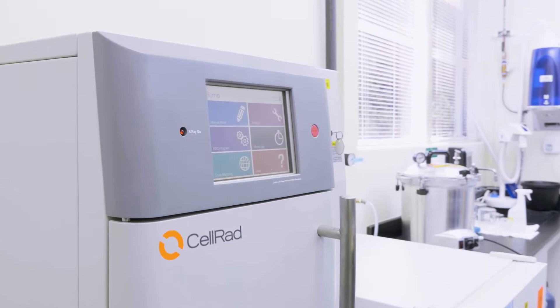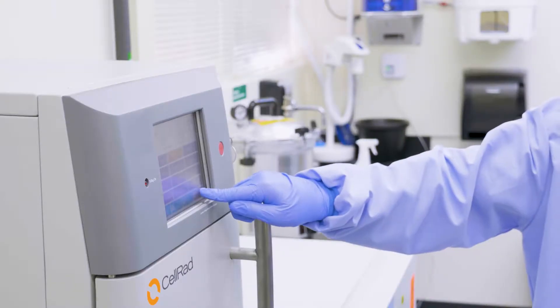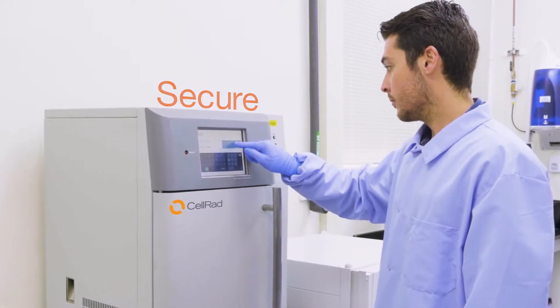The CellRad is equipped with a touch screen control panel which allows for complete exposure settings and user account control. Each user is assigned an individual user name and password that governs access to the intuitive CellRad user interface.